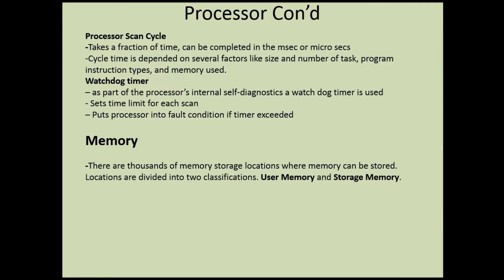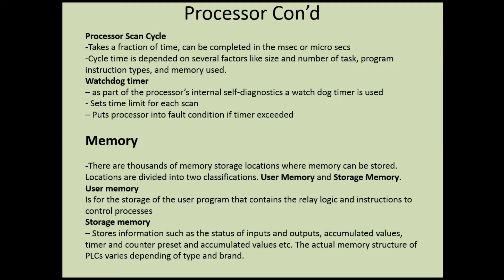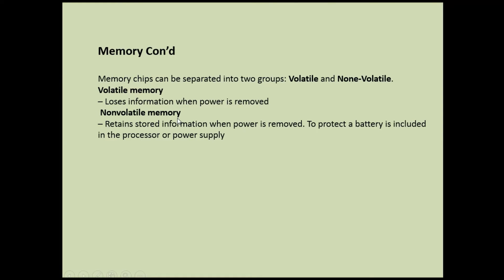There are thousands of memory storage locations where memory can be stored. Locations are divided into two classifications: user memory and storage memory. User memory is for storage of the user program that contains relay logic and instructions to control the process. Storage memory holds information such as the status of inputs and outputs, accumulated values of timers and counters, presets and accumulated values, etc. The actual memory structure of the PLC varies depending on the type and brand. Memory chips can be separated into two groups: volatile and non-volatile. Volatile memory loses information when power is removed; non-volatile memory retains stored information when power is removed. To protect data, a battery is included in the processor or power supply.